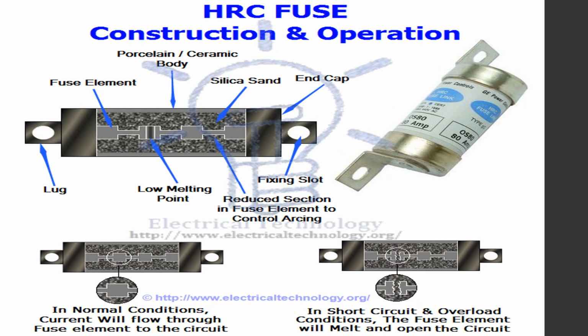The figure here depicts the HRC fuse construction and operation. As already said, the fuse wire is not a complete wire. It is made up of various sections, and these sections are joined together with the help of tin joints. The silica sand is used as an arc quenching medium, and both the fuse wire and the arc quenching medium are enclosed in the ceramic body. In the figure below, in normal condition the current will flow through the fuse element to the circuit, whereas when a fault occurs, in a case of short circuit or overload conditions where the current value exceeds beyond its predetermined value, then the fuse element will melt and open the circuit.